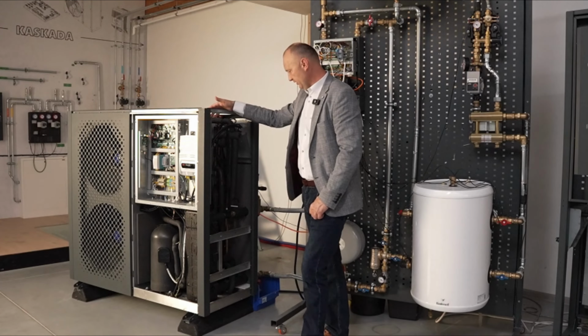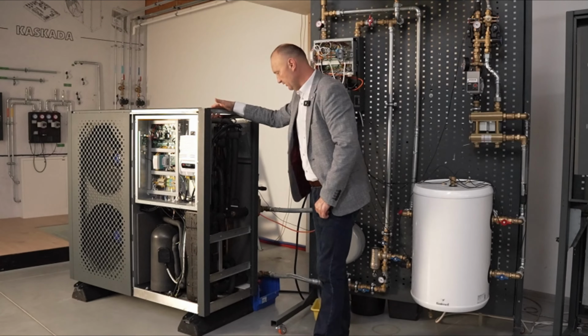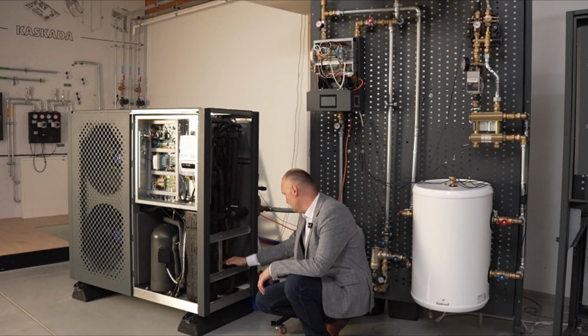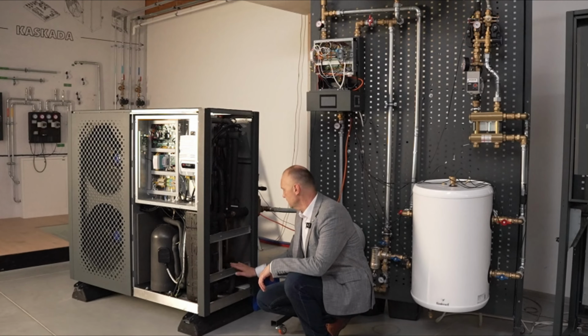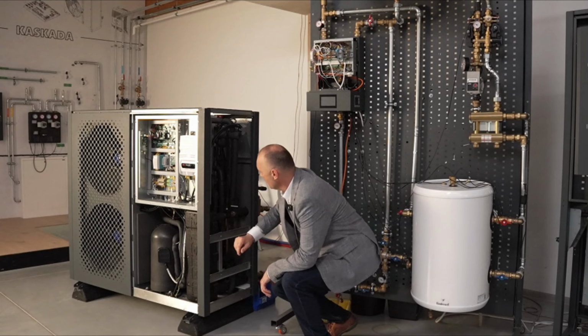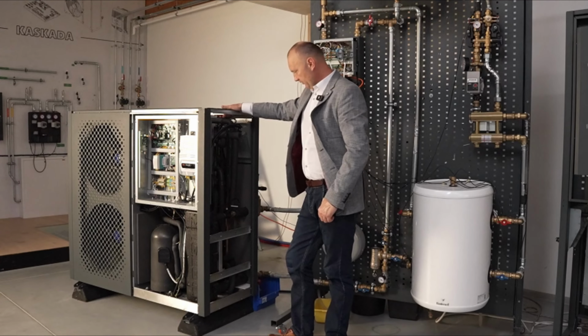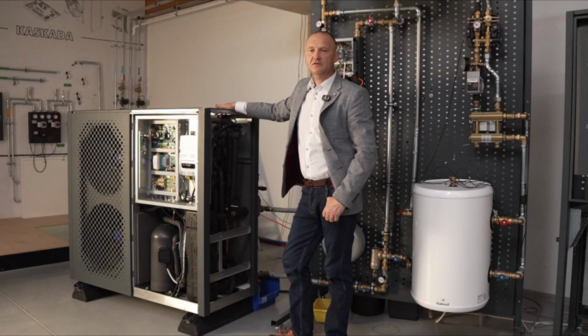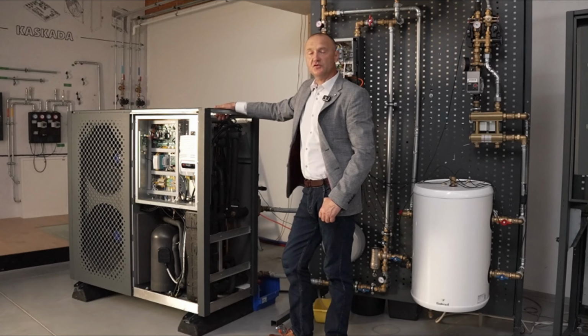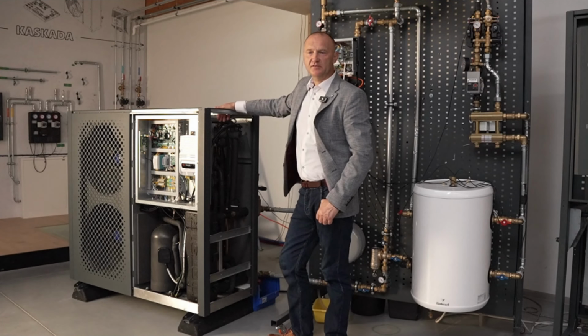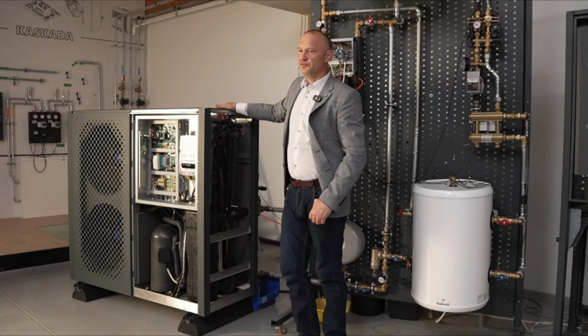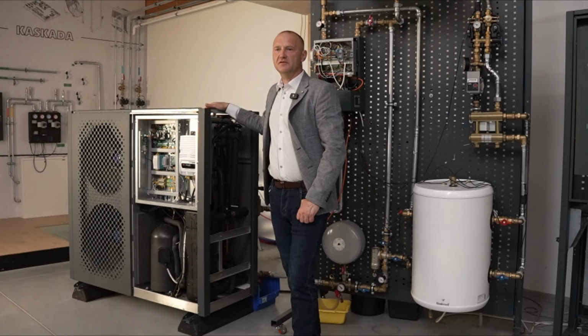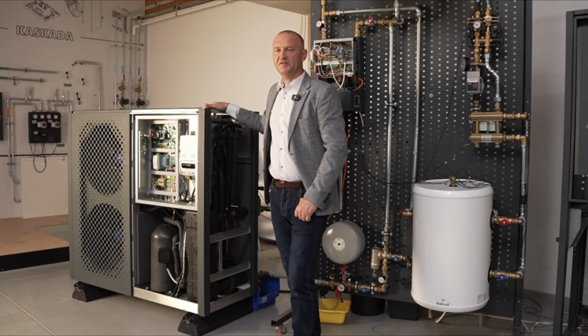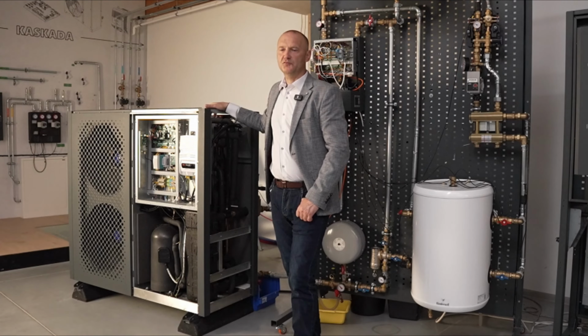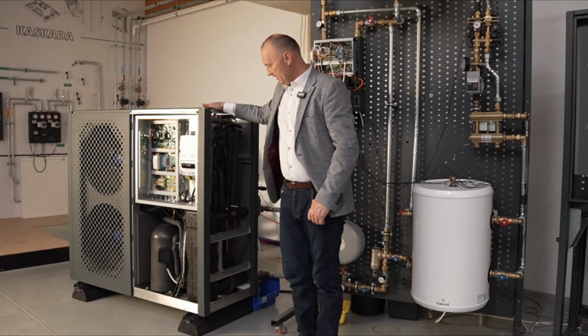Of course, the unit also features a range of other refrigeration automation components, such as a liquid receiver, a liquid refrigerant separator, or, for example, a 4-way valve, which is used to reverse the cycle. So these are some things that are, let's say, standard. However, the liquid separator we use isn't entirely standard because our device uses a liquid separator with a regenerative heat exchanger. This is a specially designed device, a unique construction that not only allows it to catch, as its name suggests, acting as a liquid separator, meaning to extract liquid, but also can be used for heat exchange.